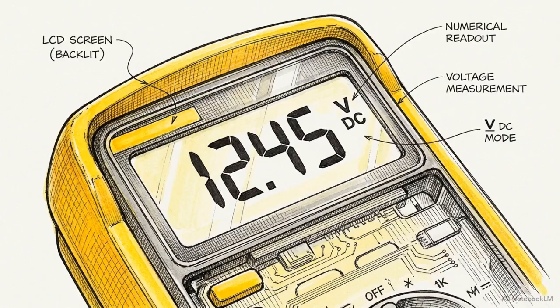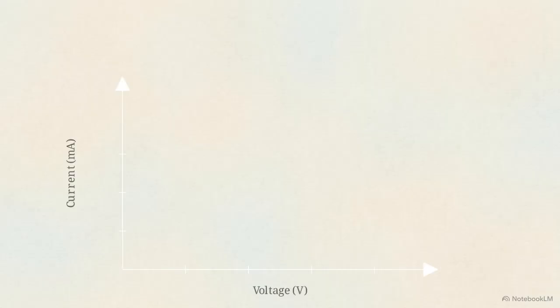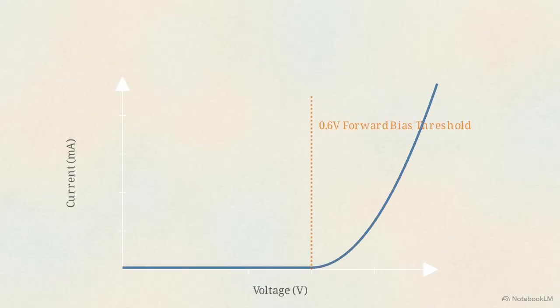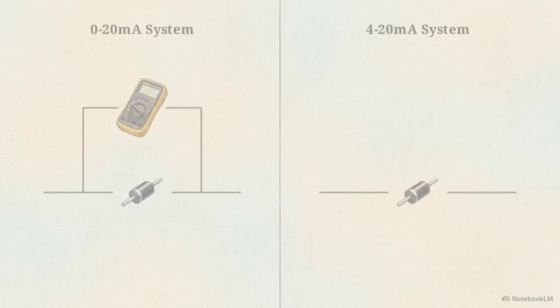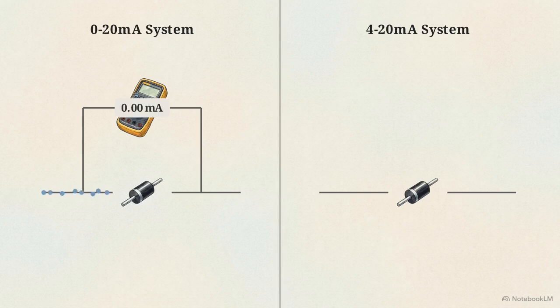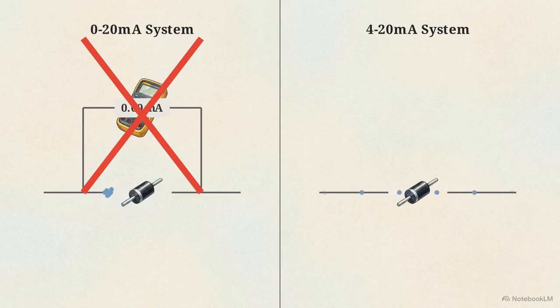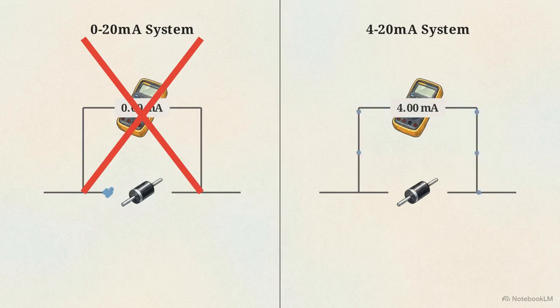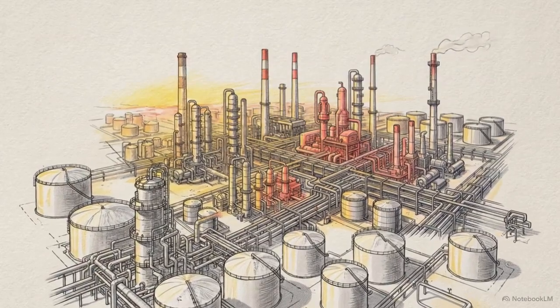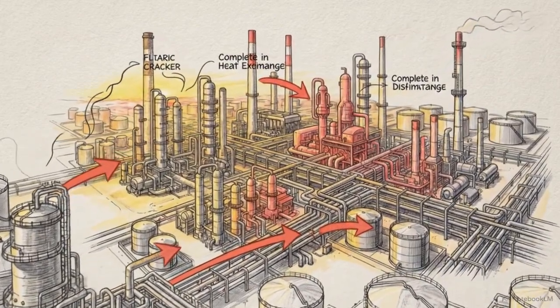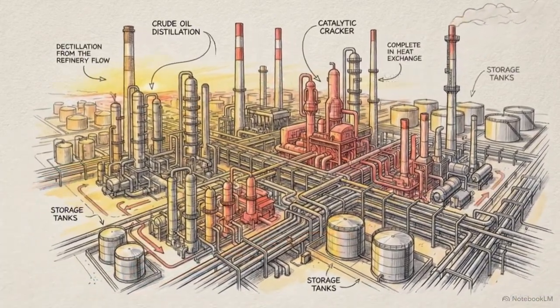This troubleshooting exploit relies entirely on the 4 milliamp live zero. A silicon diode requires about 0.6 volts of forward bias to conduct at all. It physically cannot operate if the current drops too low. If this were a 0 to 20 system, any reading below a half milliamp would lack the energy to forward bias the diode. The measurement would fail, showing zero current even when a small signal was actually flowing. The 4 to 20 milliamp loop survives as a perfectly balanced ecosystem where physics, diagnostic safety, and power distribution seamlessly interlock.